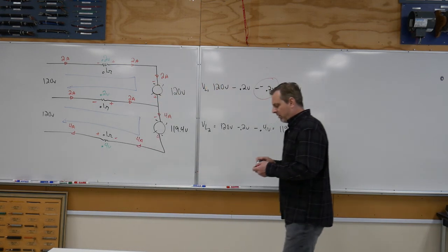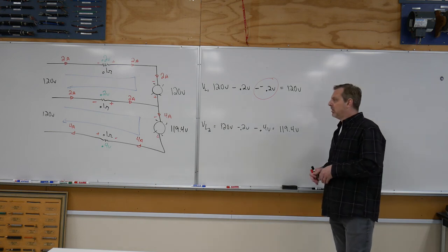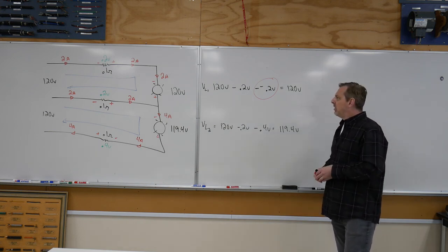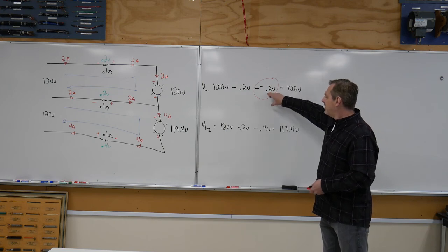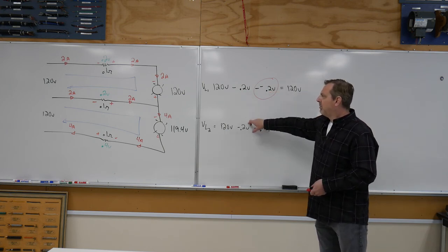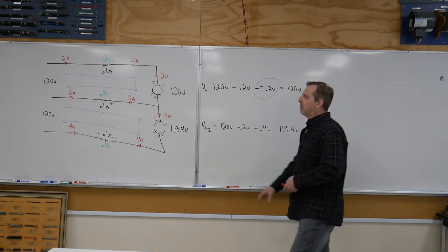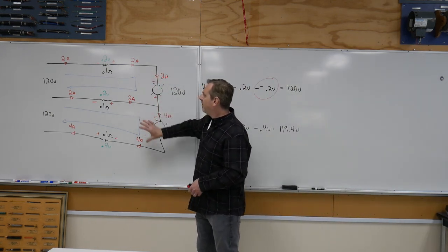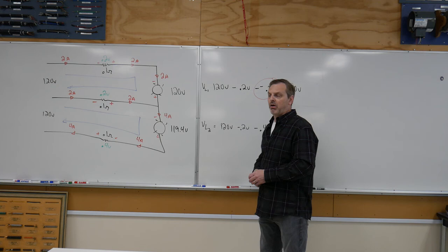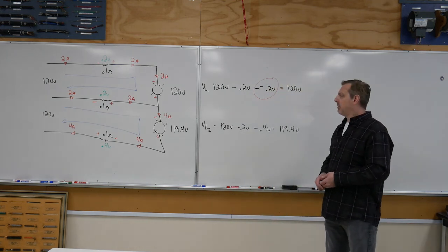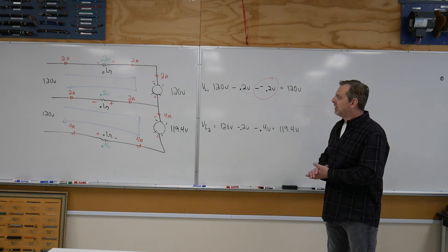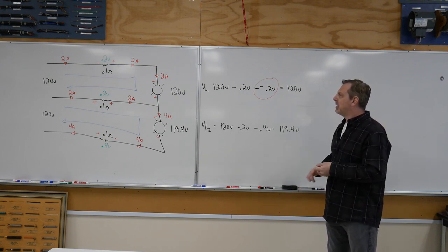That's pretty straightforward. Okay? So in this circumstance, this circuit, we had a voltage rise and a voltage drop, both on the neutral. It just depended on which side we were looking at. So you have to be prepared to solve for those. All right? And we'll do some further explanation on that in the Learning Hub. But that's a straightforward example of a 3-wire circuit using line conductor resistance into the equations as well.